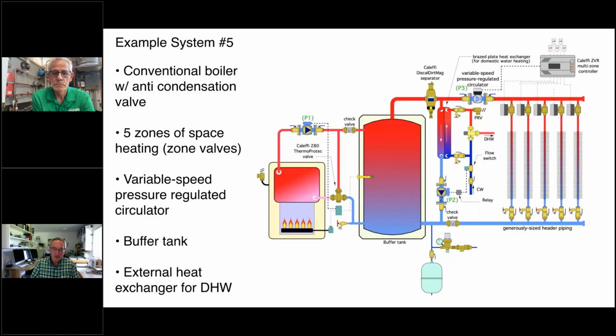And there's actually products on the market, both the chemical and the little submersible pump in a 5-gallon pail, basically, to clean that heat exchanger. Worst case, if you really scale it up, you can replace it. With an indirect, if you scale up the coil, you have to put a new tank in. There's no access to cleaning that coil or replacing that coil. So it's again another little detail worked in with some zone valves over here. We talked about the purging valves on the return and so forth.